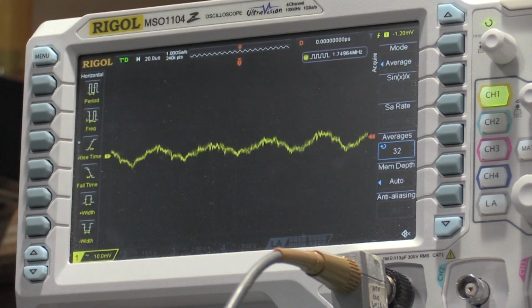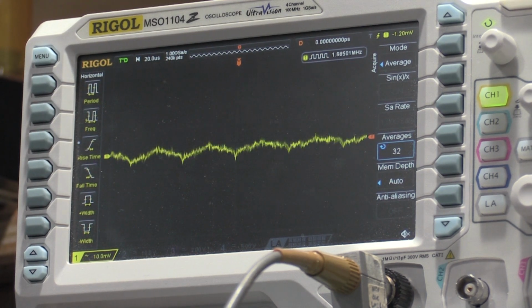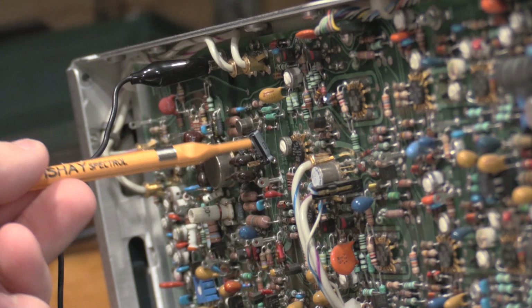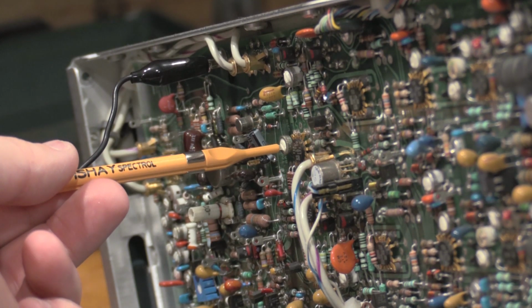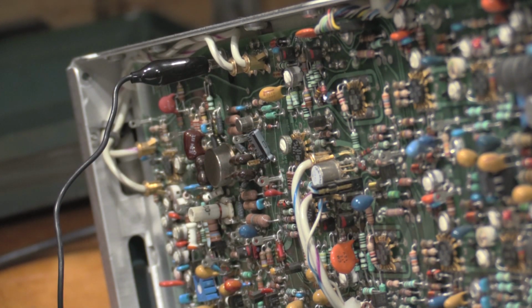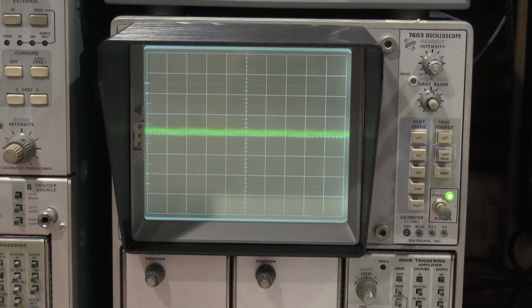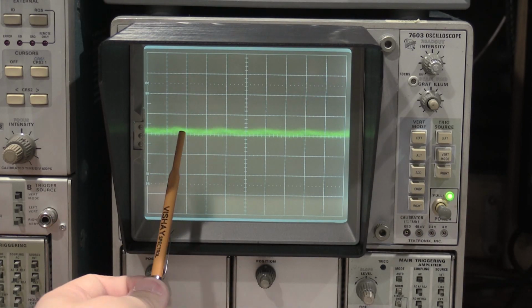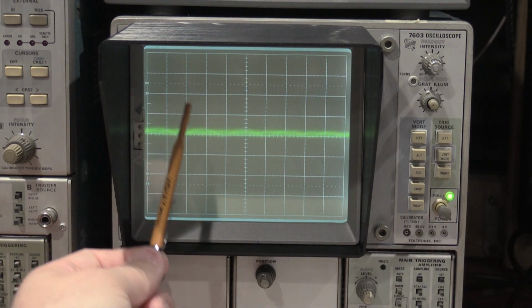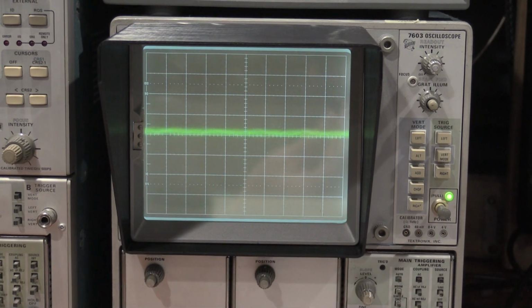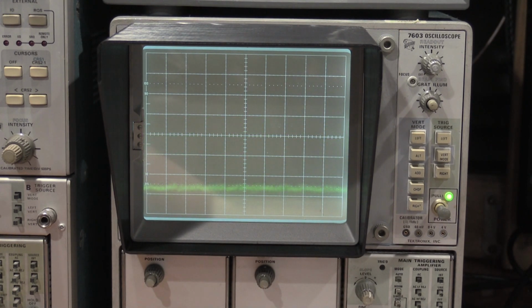568. And we have a little bit of noise on the signal, so I need to null that out using the trigger gain control. Trigger gain control is over here. Trigger gain is this adjustment right here, so we'll be nulling that out and then going from there. Alright, I needed the analog scope to get the best result. If I adjust it more, the trace will move up and down. Actually, I can show that here real quick. So if I adjust it up, the trace will move up, and you can see the waveform open up just a little bit, and if I go past it, it'll really open up.